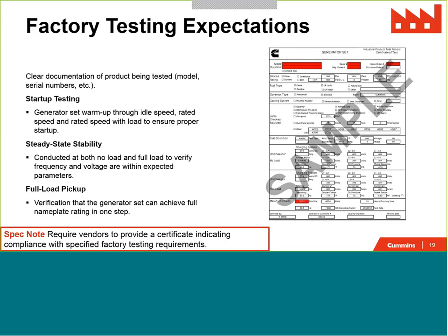So some things that you'll see here for factory testing. One, first and foremost, you should be able to at least request documentation of the product being tested, and that should be down to the model and serial number of the product that you're being tested. This should be easy to request from any generator set manufacturer. You'll also see standardized tests from the generator set manufacturer. This could include startup testing, steady state stability, and full load pickup. These are fairly straightforward, and these are something that the generator set manufacturer is going to conduct in order to verify the performance in the unique configuration of the product. Again, we always recommend that you require vendors to provide a certificate or a letter or statement indicating compliance with the factory testing that you have specified.